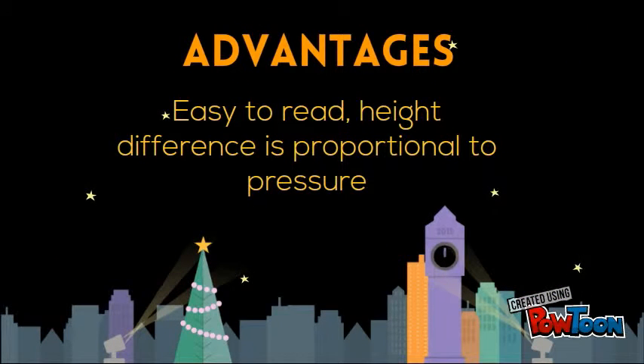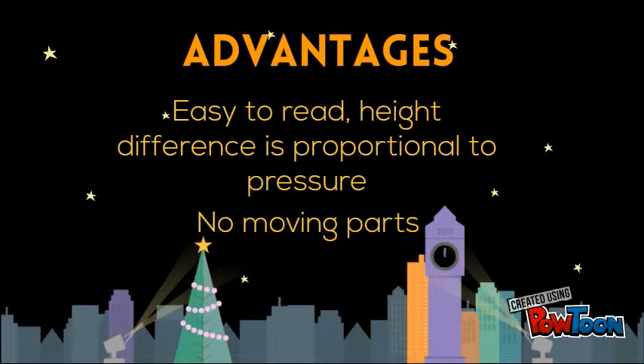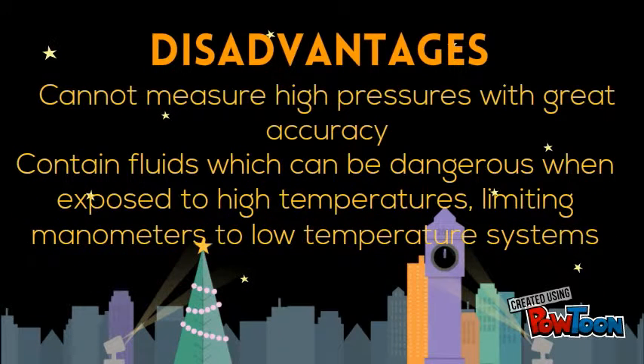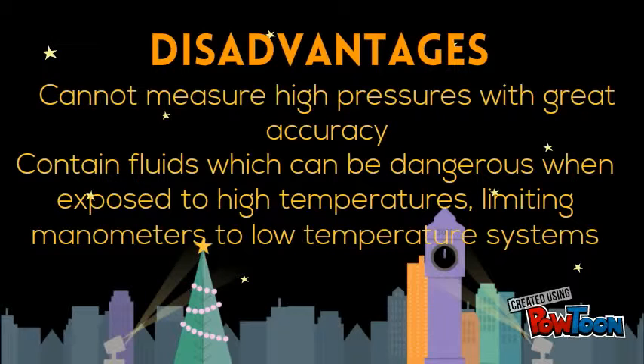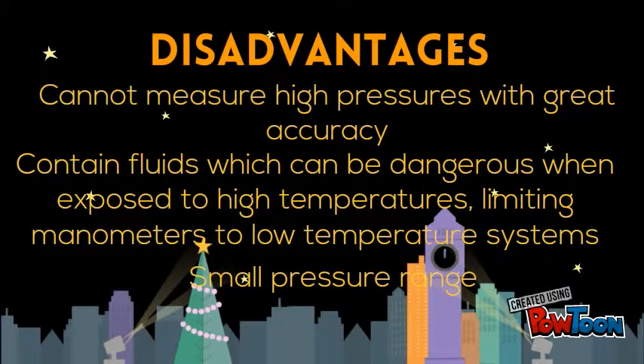Advantages of manometers include: easy to read, height difference is proportional to pressure, and no moving parts. Disadvantages include: cannot measure high pressures with great accuracy, contain fluids which can be dangerous when exposed to high temperatures, limiting manometers to lower temperature systems, and a small pressure range.